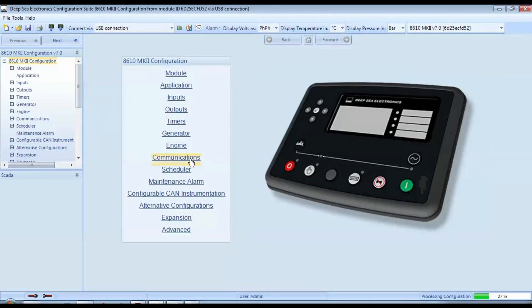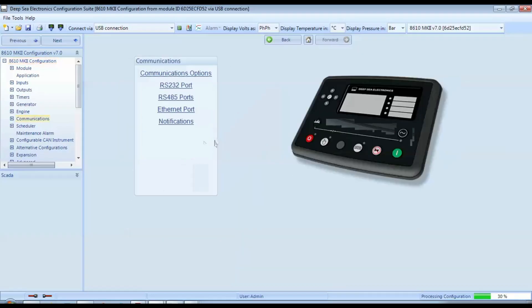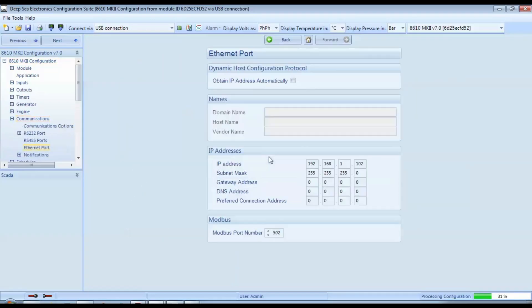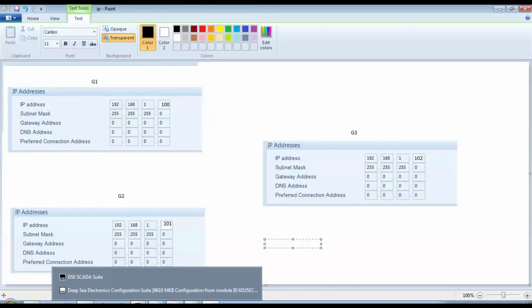Now go to Communications > Ethernet port. Here, we must adjust the IP address and subnet mask. For example, controller for generator number 3: set IP to 192.168.1.102, subnet mask 255.255.255.0.